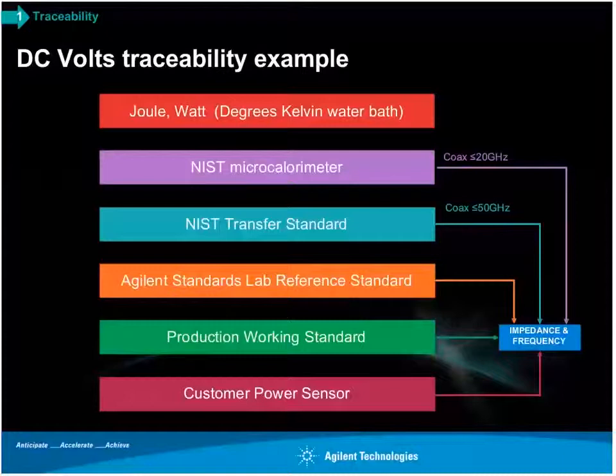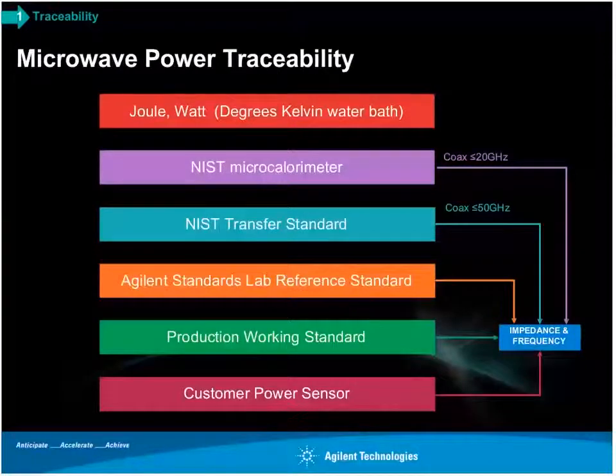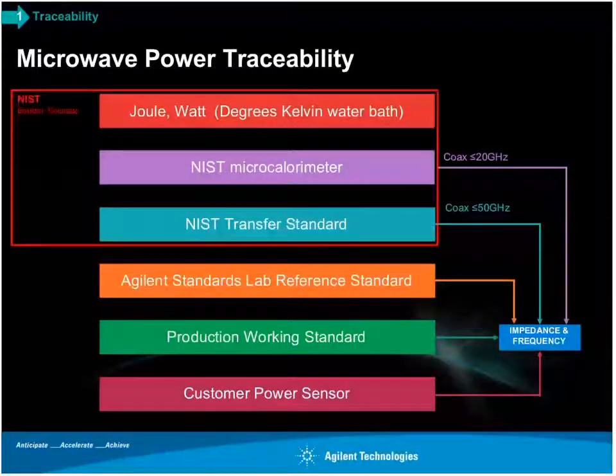I'd like to show you a little bit about microwave power. Obviously, anytime you walk up to an RF microwave system, I, as an engineer, oftentimes think, okay, now how can you prove that everything here is working correctly? In almost every automated system, there's an engineer somewhere who's written a system performance test, and almost always they start with the 50 megahertz reference on the power meter, because that is the closest thing in most instrument test stations to a primary standard. Of course, it's 5 or 6 steps away, but in a given test system, it's the most accurate reference.